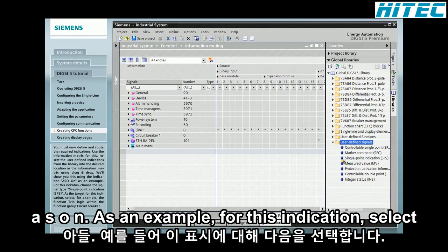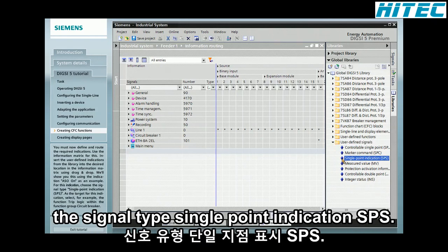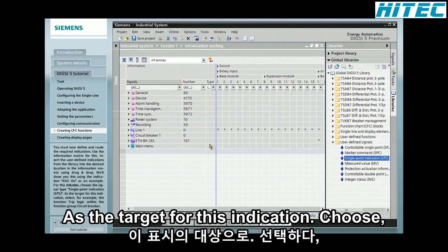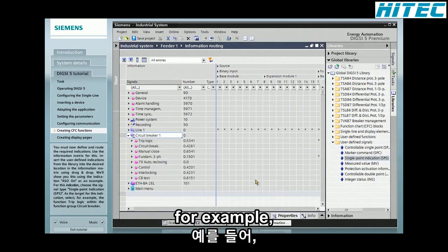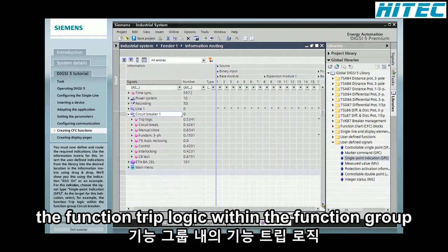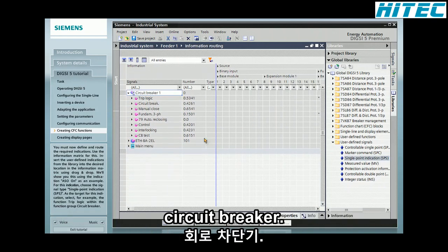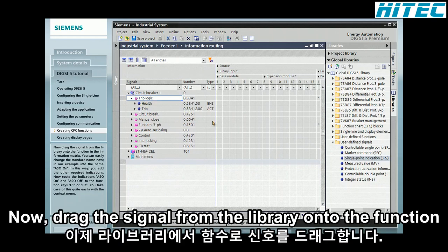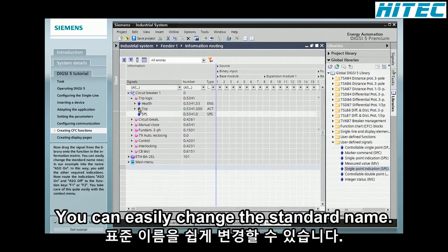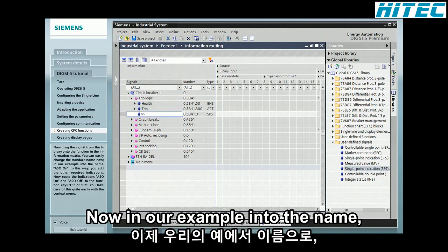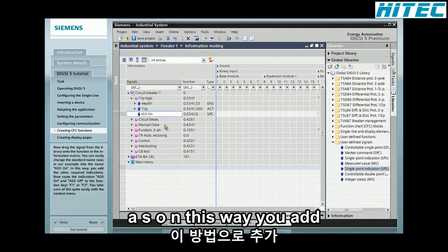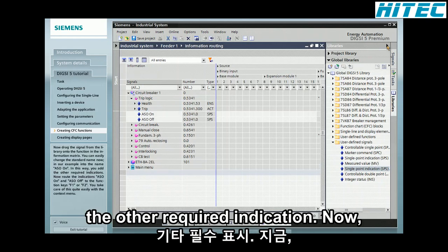For this indication, select the signal type single point indication SPS. As the target for this indication, choose, for example, the function trip logic within the function group circuit breaker. Now drag the signal from the library onto the function in the information matrix. You can easily change the standard name now, in our example, into the name ASO on. This way you add the other required indications.